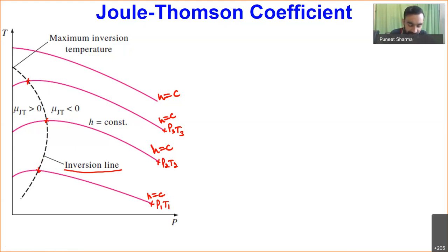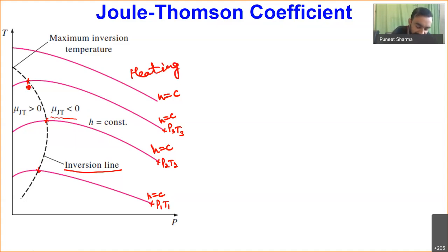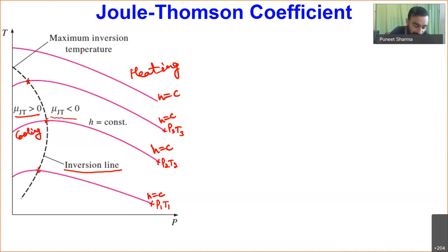On the right-hand side of the inversion line, the Joule-Thomson coefficient is negative, so we have heating of the working medium upon expansion. On the left-hand side, the Joule-Thomson coefficient is greater than zero, so we have cooling of the working substance. This is the region where we must operate our refrigerants — while doing throttling in case of refrigerant, we have to operate in this cooling region.